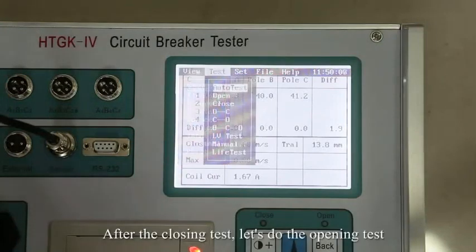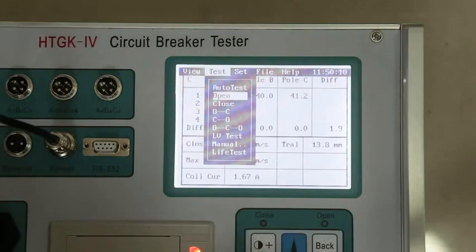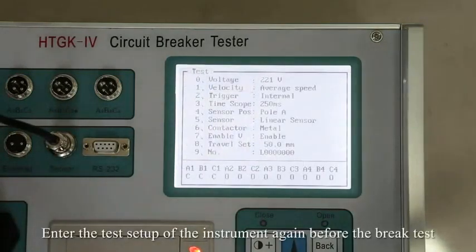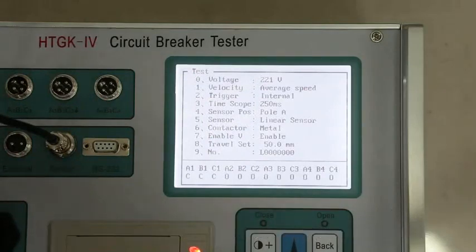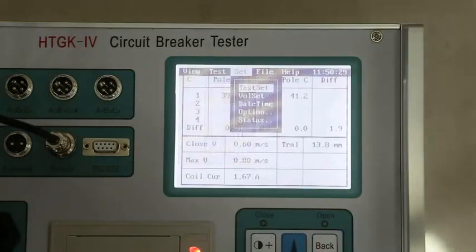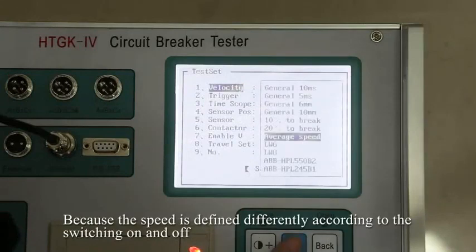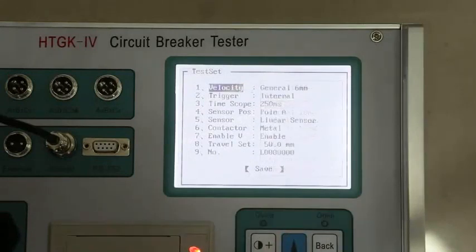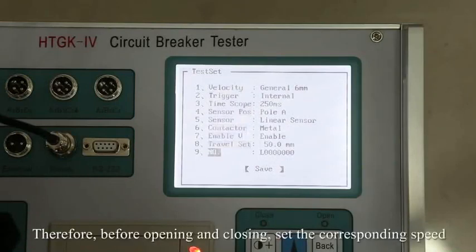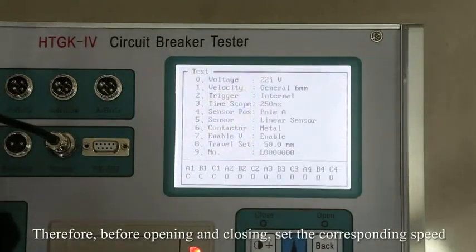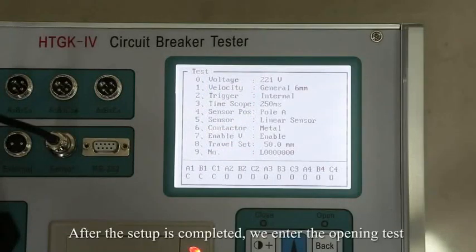After the closing test, let's do the opening test. Enter the test setup of the instrument again before the opening test. Change the speed to 6 mm. After setting up, we select Save. Because the speed is defined differently for switch opening and closing, before opening or closing, set the corresponding speed. After the setup is completed, we enter the opening test.